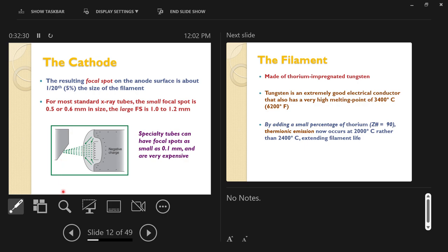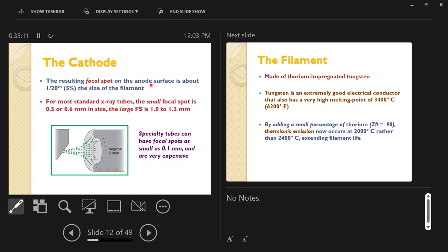The focal spot is where the electrons strike the anode face. The anode face is angled slightly. The focal track — the track worn into the anode — has a width that is always smaller than the filament length because of the focusing effect. Roughly, the focal spot on the anode surface is about five percent the size of the filament — about one-twentieth of that length.